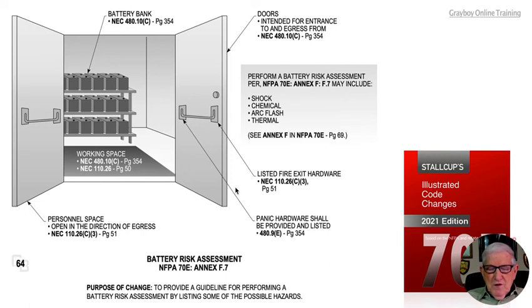Now notice that we could also check in the Annex D to 70E, D.5.3 on page 67, and we have formulas there and a means to calculate estimated energy. But to get the available short circuit current accurate, you need to check this out with the manufacturer of the battery bank that you see here, and they can tell you exactly what it would be.